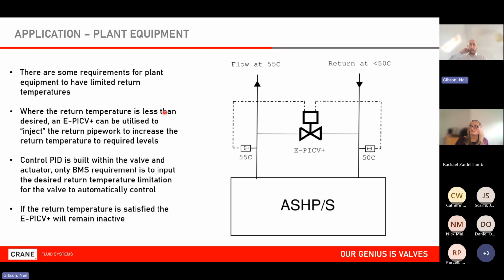The very last slide is just an interesting live example that we worked on. So we were requested to support in a project where they were installing heat pumps, and the heat pump delta T was tiny. It was 5 degrees. In this example, they were going out at 55 and returning at 50. That was the requirement. The problem was that the system was designed around a delta T of 10. So it was going out at 55, but it was coming back at less than 50. It was coming back at 45. And they had very specific instructions from the heat pump manufacturer that it must come back at 50.